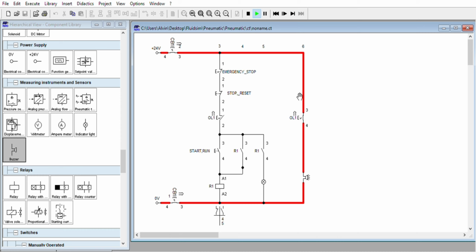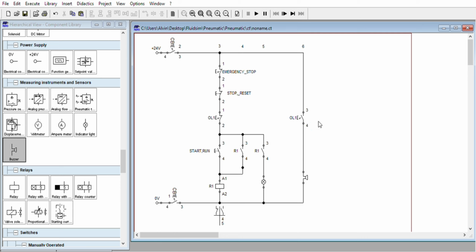So that means we have a tripping action in our circuit. So what are we going to do? You don't have to reset the thermal overload relay. That is a wrong procedure. If there is a tripping action, there must be trouble in the circuit. That means we are going to turn off the main circuit breaker. In this case, we have the auxiliary circuit breaker first. And repair the trouble. What causes the thermal tripping? Turn off. And at that time, we are going to reset the thermal overload relay. Go to the specification of the motor, go to the specification of the setting of the thermal overload relay.